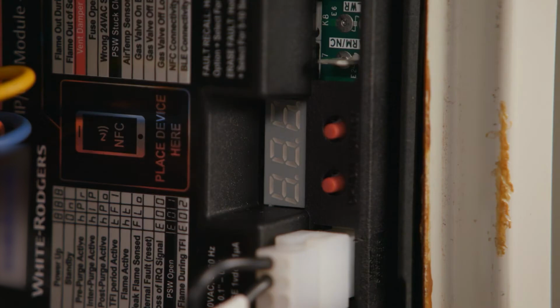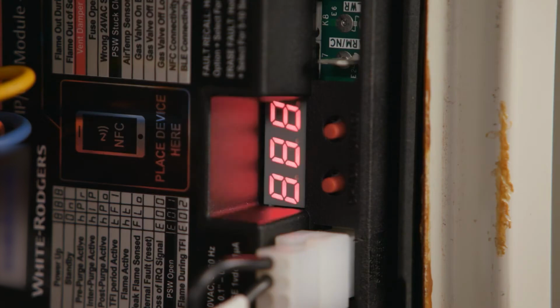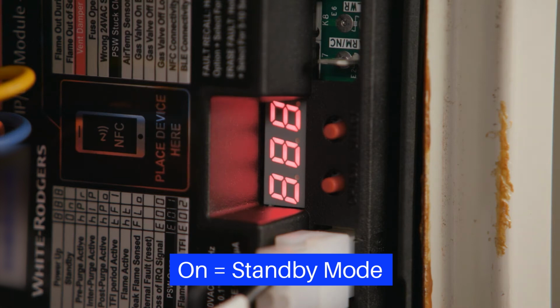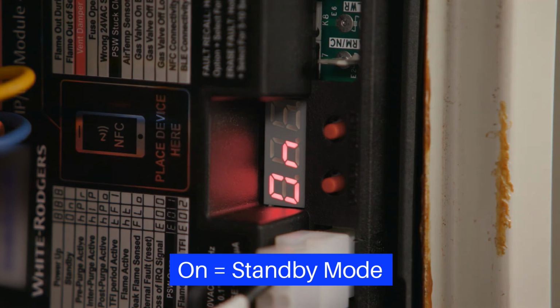Reconnect the electric power and gas to the unit and make sure the door switch is engaged. During power-up, the 3 digital LEDs will each display an 8. Once ready, the control will enter the standby mode and the LEDs will display an uppercase O and a lowercase n, indicating the unit has been powered on.